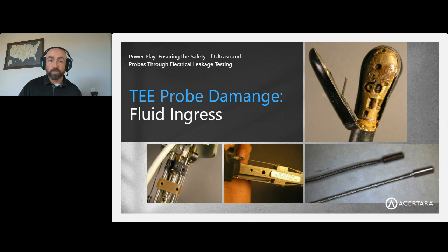Again, as soon as it's energized, you're going to run into problems if you have fluid ingress. If you catch it before that probe gets plugged in and energized, sometimes there are services that can keep that probe from being a total loss. We can fix it so that it's not broken. The fluid ingress also has an effect on the articulation components inside that TEE probe. Anything that moves, they're typically steel cables that they use inside, wound quite tightly like piano wire, and they're very susceptible to damage when fluid ingress occurs.